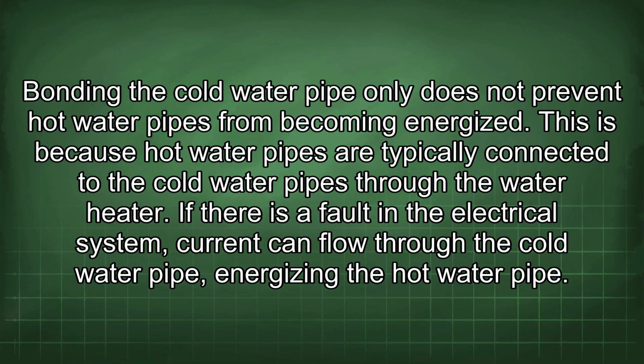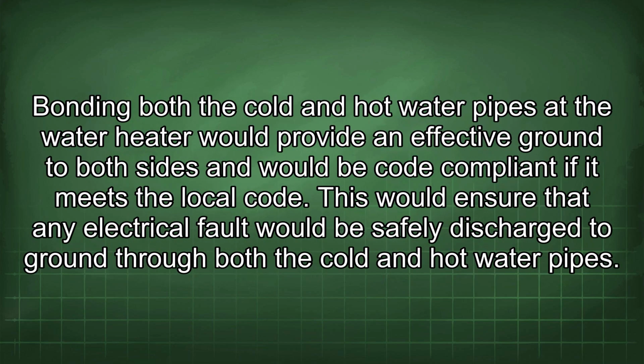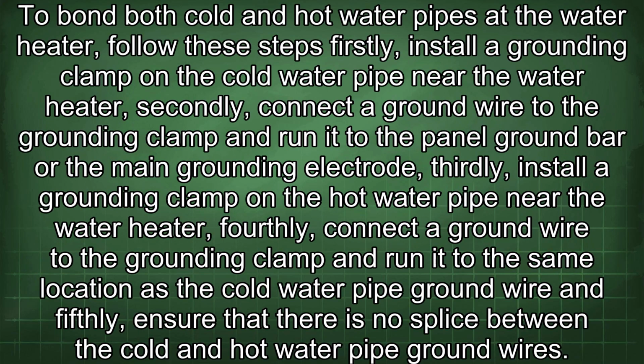Bonding both the cold and hot water pipes at the water heater would provide an effective ground to both sides and would be code compliant if it meets the local code. This would ensure that any electrical fault would be safely discharged to ground through both the cold and hot water pipes. To bond both cold and hot water pipes at the water heater, follow these steps.